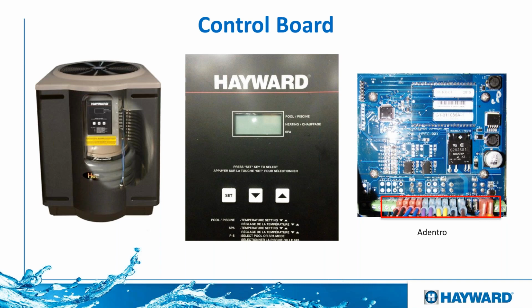Then we have, oh, by the way, HP, I'll explain a little bit more in advance, but most of the times, the issue with this is that we have a lack of flow. So I'll talk about that in a second. And then we have these two blue wires. The two blue wires are for low pressure. So when we are low on refrigerant, those two are going to open up and it will give us a code of LP. Most likely, we'll probably have a little leak or a leak of refrigerant, which means that we have to find it, fix it, and then recharge the heat pump.